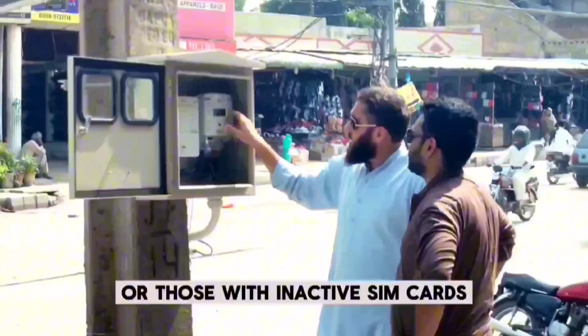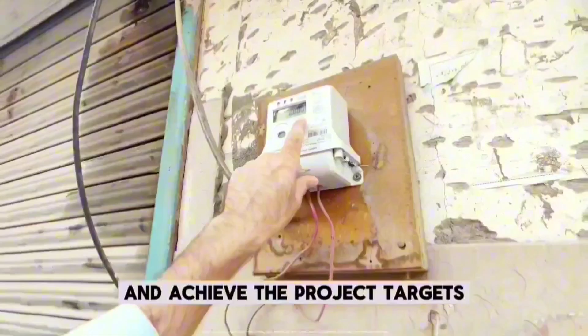Furthermore, non-commissioned DCUs or those with inactive SIM cards fail to communicate with the head-end system, causing data gaps. Transformers lacking DCUs disrupt the complete mapping of the feeder, preventing accurate assessment of feeder losses. Through meticulous monitoring and proactive problem solving, it is essential that the AMI system operates seamlessly, maintaining the project's integrity and achieving the project targets.